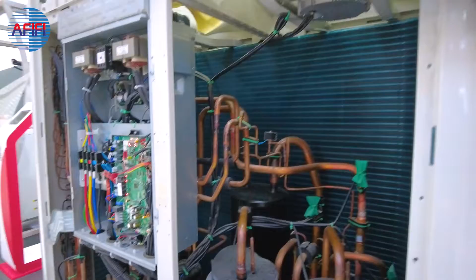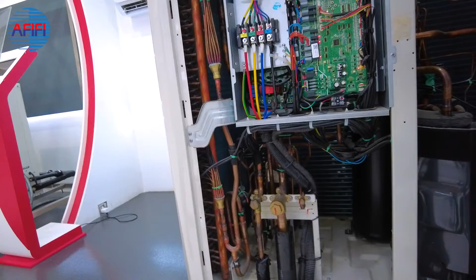Right. I was about to ask why this one is here. So we've got a capillary, then another additional expansion valve as well. That's for the heating cycle. On the cooling cycle, it'll come into the condenser, the fans would run, and subcooling would happen. Now, the biggest difference between a T1 VRF and a T3 VRF is something called a subcooler, or a plate heat exchanger. That is added on to a normal system. It adds to your condenser's capacity. It subcools the refrigerant further, so that even if the condenser is at 55 degrees Celsius, it will kick in and cool it further.